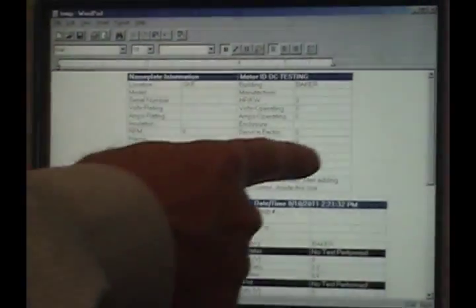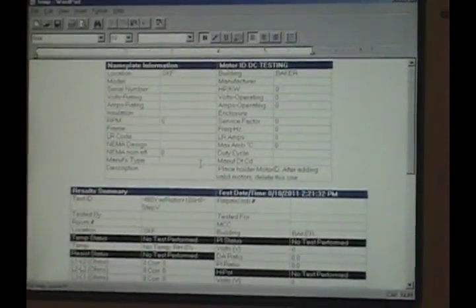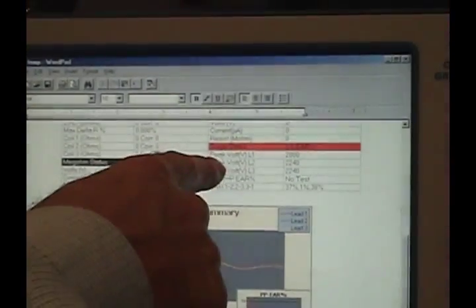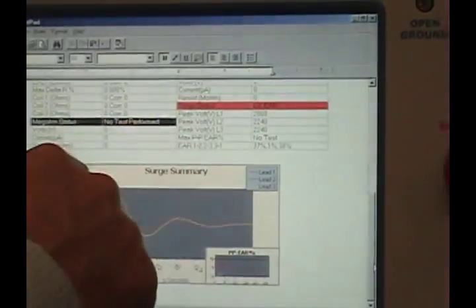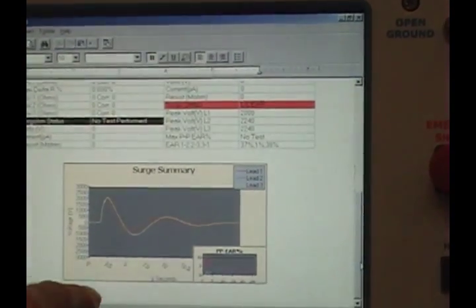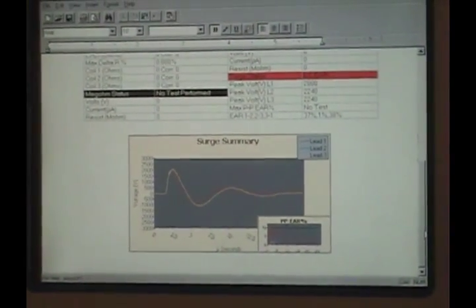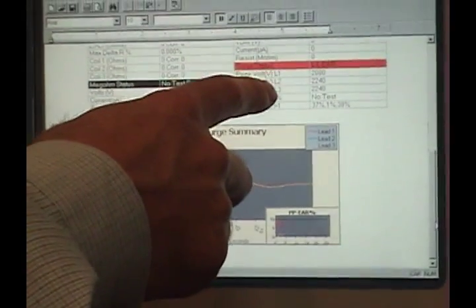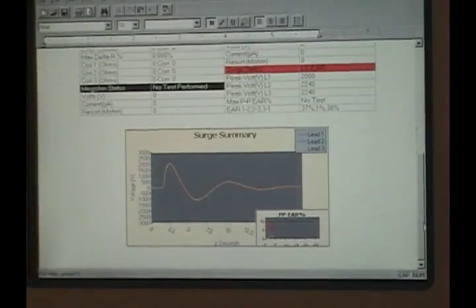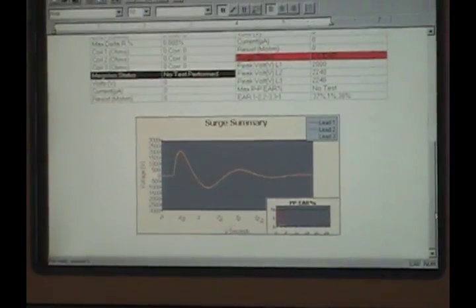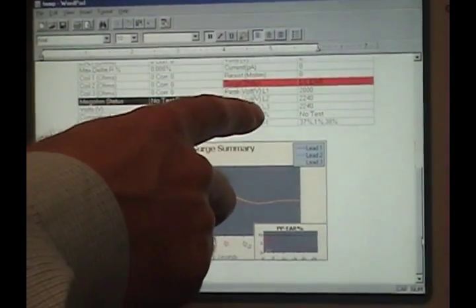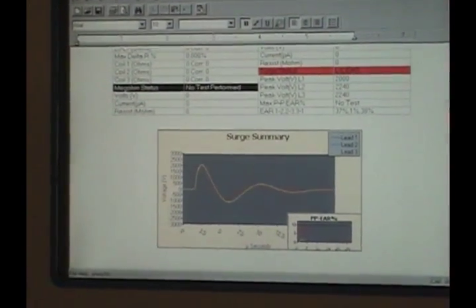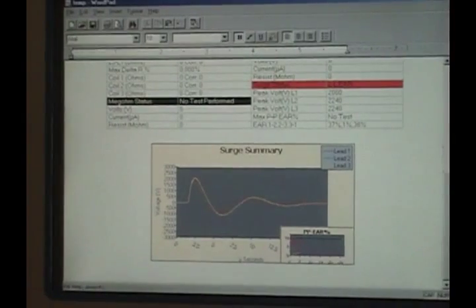This section up here will give you your nameplate information. Here is your surge results. Lead 1 would be your reference waveform or your master waveform. And then lead 2 and lead 3, your reference waveform would also be considered your good waveform. And then lead 2 and lead 3 would show you your bad waveforms. You can display that, and then you can display that to your customer.